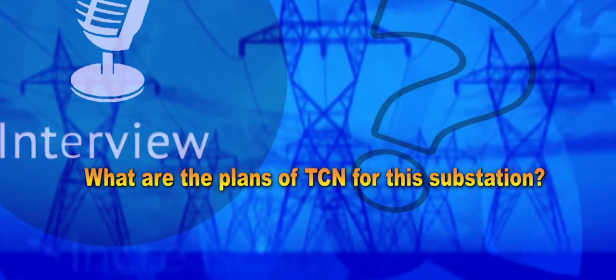What are the plans of TCN for this substation? Those 2 by 15 MVA transformers are 132/11 kV transformers, which is actually the only one existing, I think, in our network, and we don't want to be operating at that level. So we want to change those 2 by 15 MVA 132/11 to 2 by 60/33 kV, and bring out an outdoor 33 kV switchyard to accommodate that, and do some adjustment on the bus. The control room will also have to go through rehabilitation, a facelift, and changes.